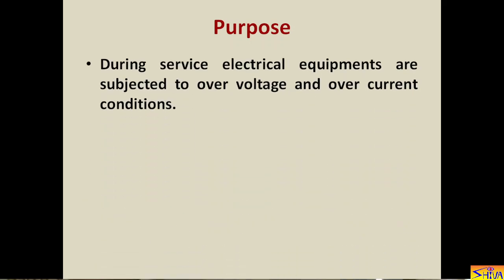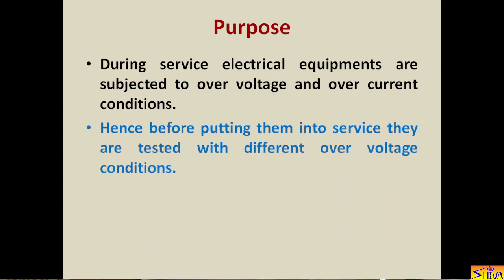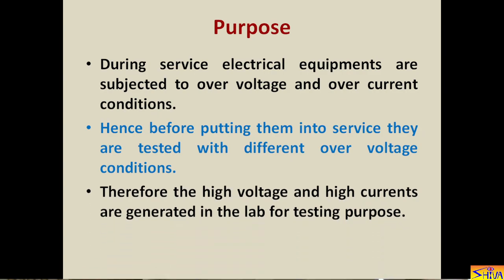Now let us see the purpose of generating high voltage and high current. During service conditions, electrical equipment is subjected to over-voltage and high current conditions. These over-voltages may be at power frequency, lightning over-voltage, switching over-voltage of impulse nature, or switching over-voltage at high frequency. Similarly, when a short circuit occurs the equipment must bear that short circuit current for a short duration, and when lightning over-voltage occurs, heavy lightning current flows and the equipment as well as the lightning arrester must bear that high current for a very short duration. Hence, before putting equipment into service, they are tested with different over-voltage conditions. Therefore, high voltages and high currents are generated in the lab for testing purposes.